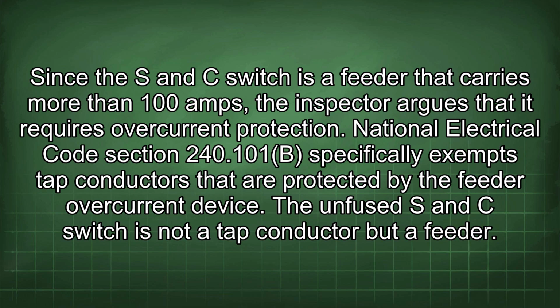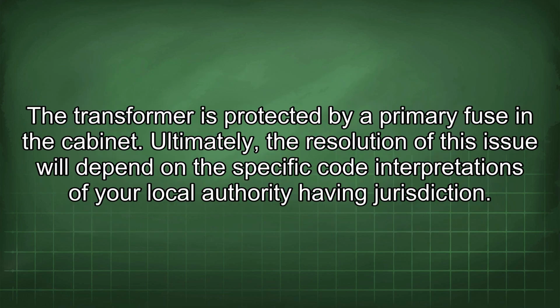240.101b specifically exempts tap conductors that are protected by the feeder overcurrent device. The unfused S and C switch is not a tap conductor but a feeder. The transformer is protected by a primary fuse in the cabinet. Ultimately, the resolution of this issue will depend on the specific code interpretations of your local authority having jurisdiction.